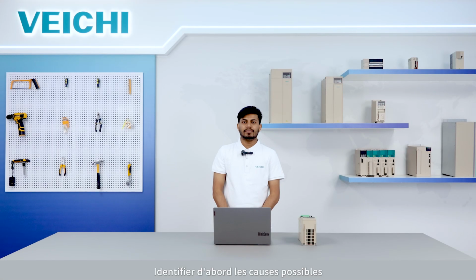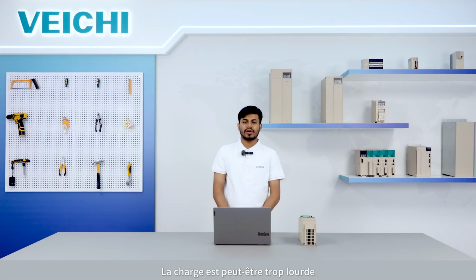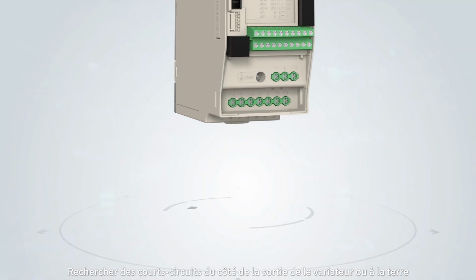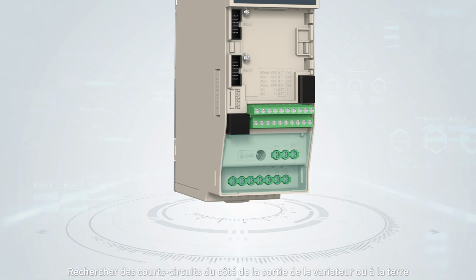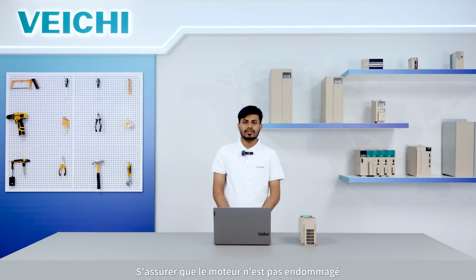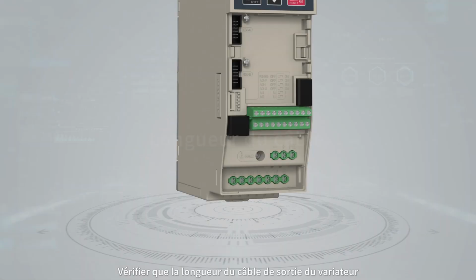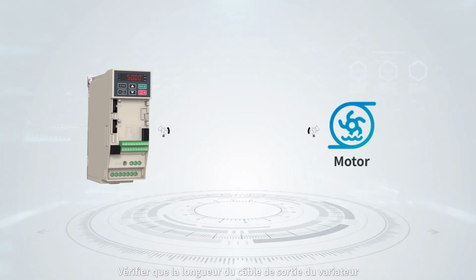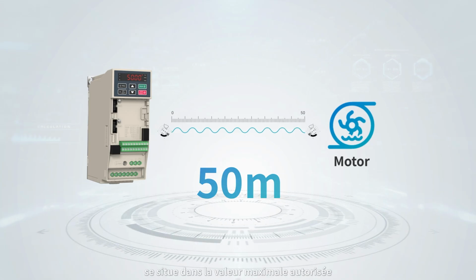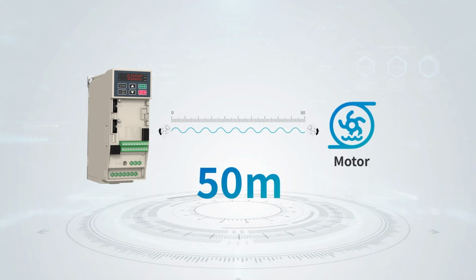First, identify possible causes. Excessive load. The load is too heavy. You can reduce the load or you can replace high capacity inverter. Short circuit. Look for short circuit on the inverter output side or to ground. Motor damage. Ensure motor is not damaged.